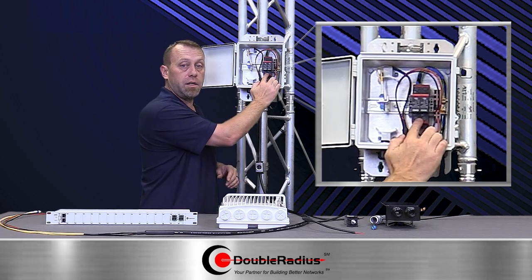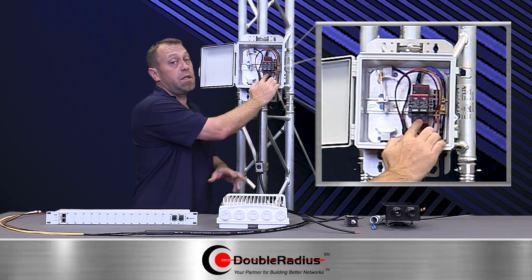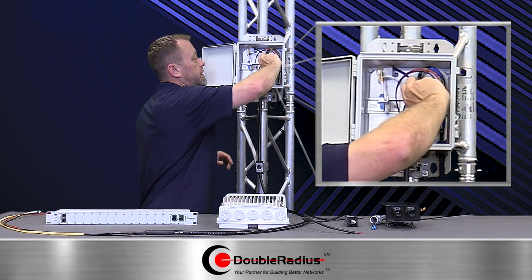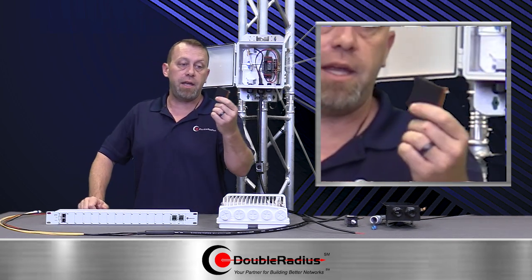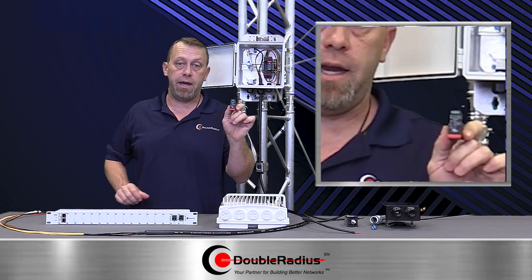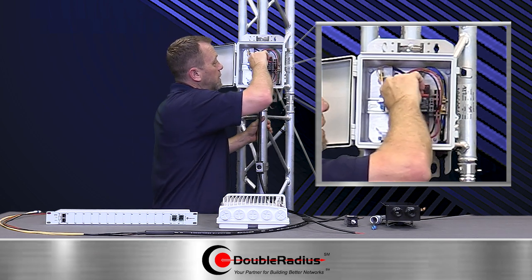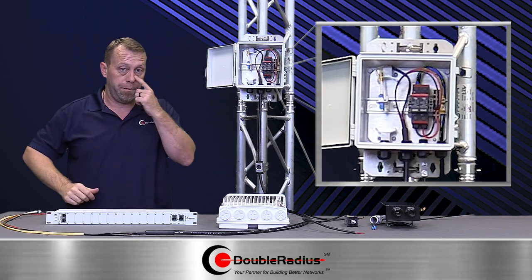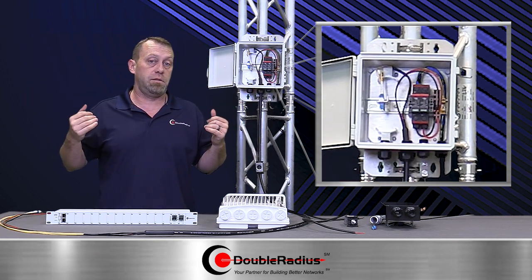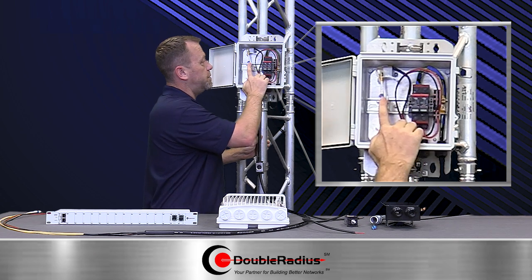This is a Transtector DC surge protector rated for 48 volts — let's focus on 48 because that's pretty much the standard these days, though there is a 24-volt version. The main guts of it has a green window in the front that tells you it's good to go. If it turns red, there's a problem and you need to swap it out — but you don't have to swap the whole box, just this little piece, which snaps in quick and easy. This actually runs in parallel with your power.